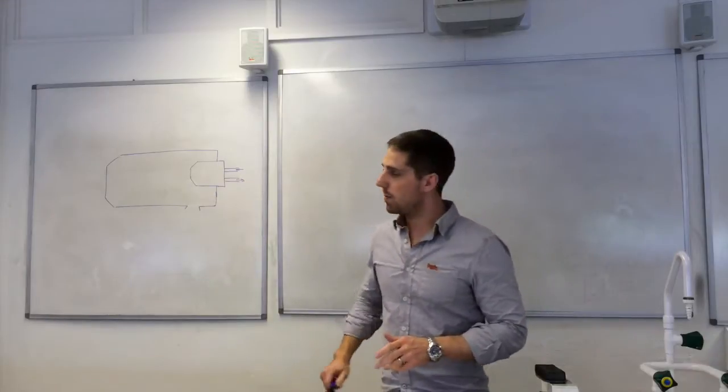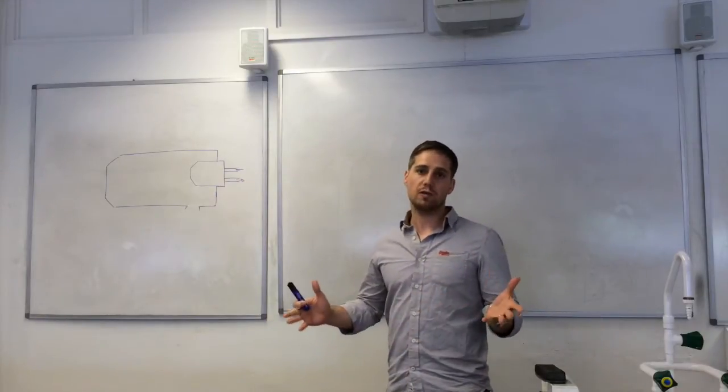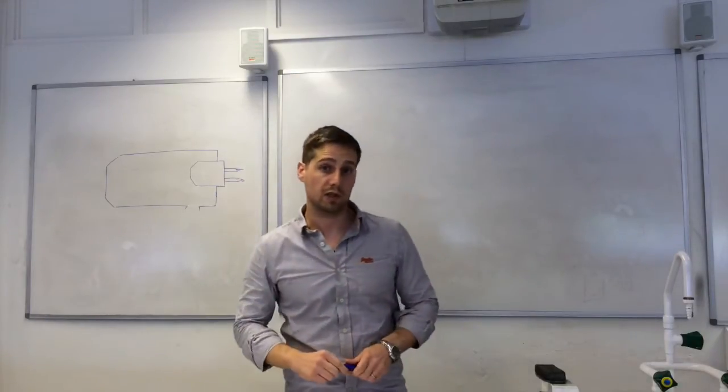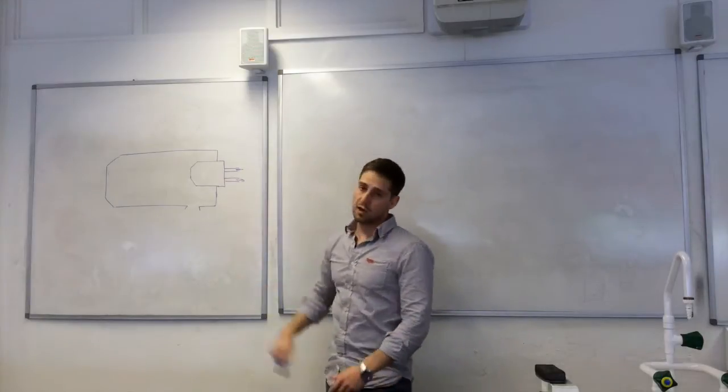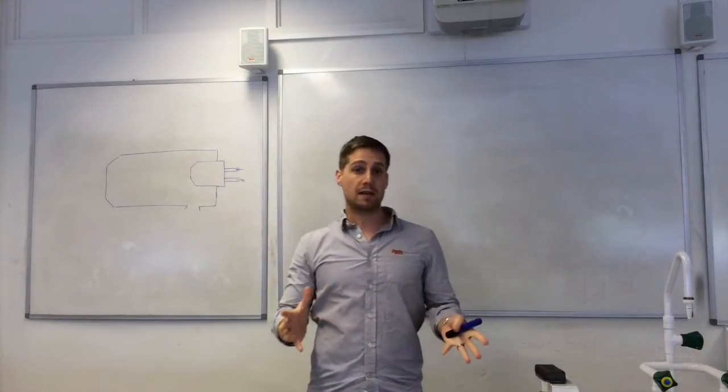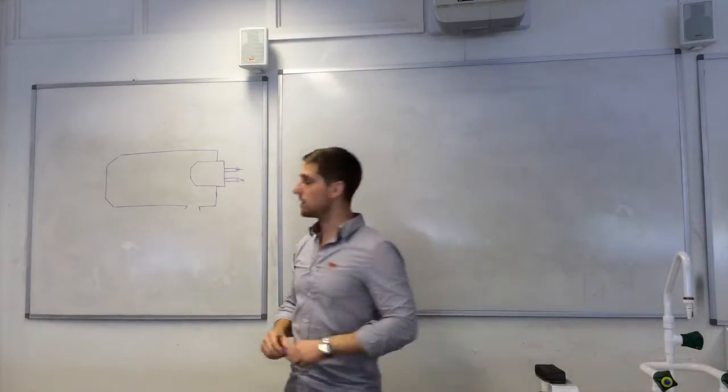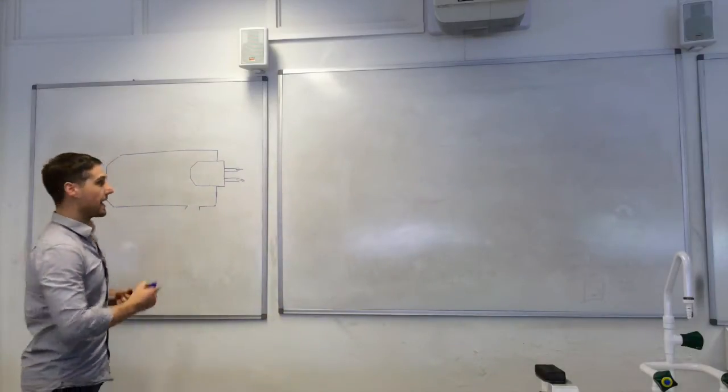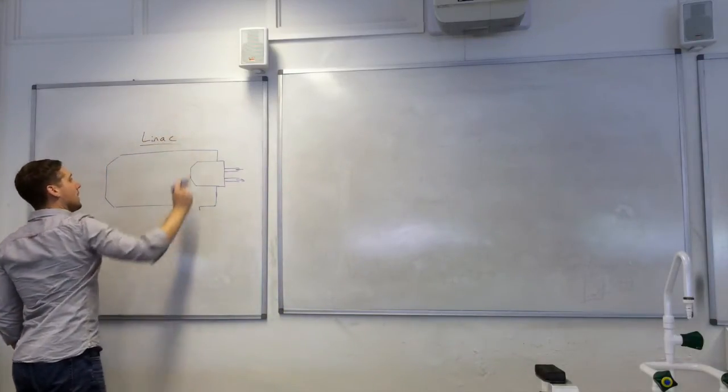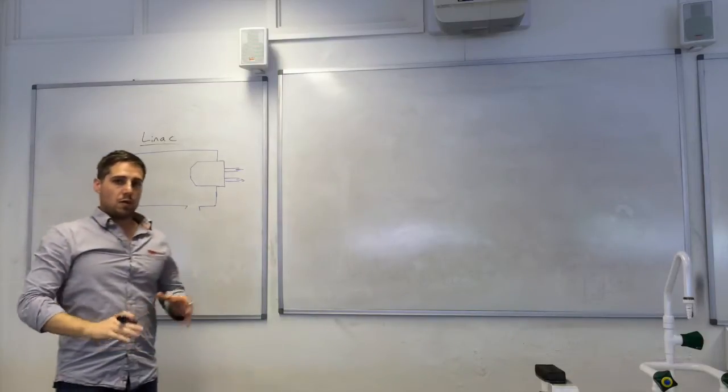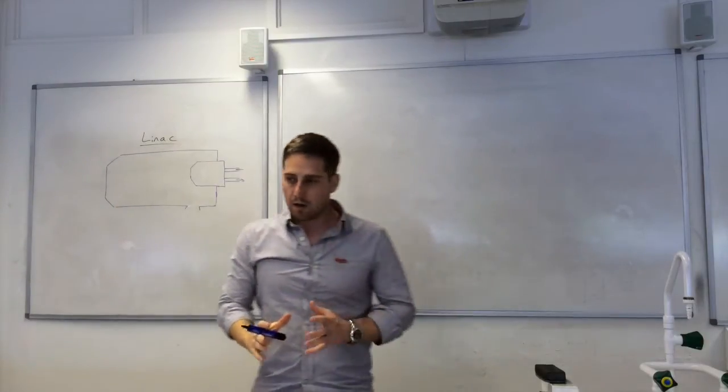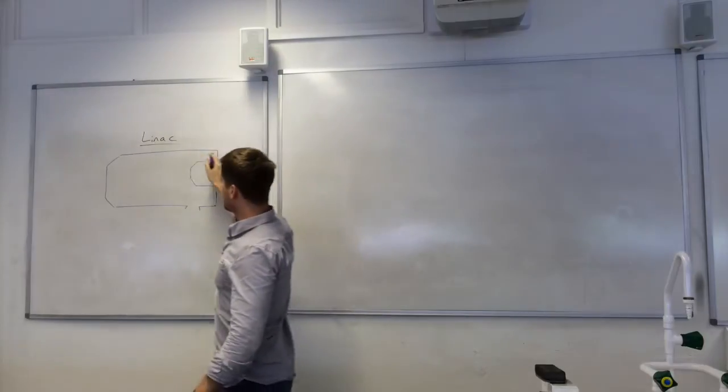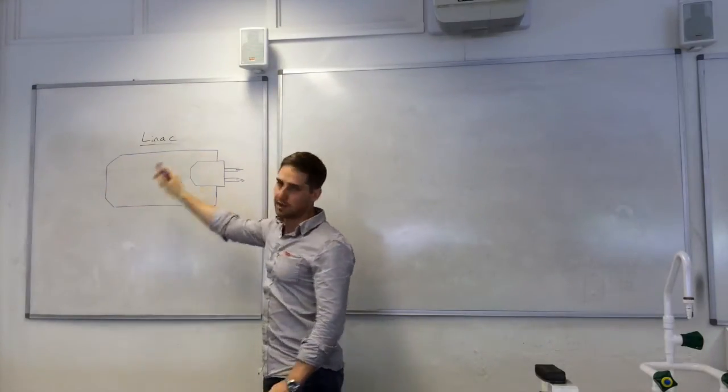We're going to kick off by explaining how we produce X-rays for megavoltage therapy. Starting with this diagram here, this is a schematic diagram of a linear accelerator, sometimes called a linac for short. What we do with the linear accelerator, it all takes place in this lead casing here.